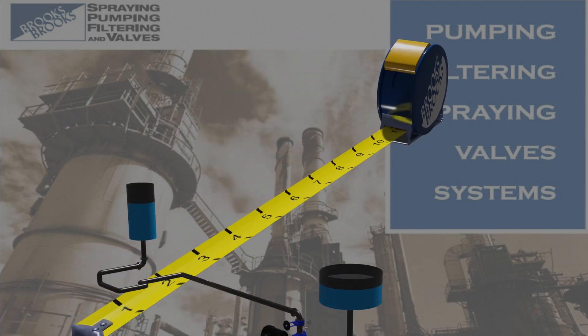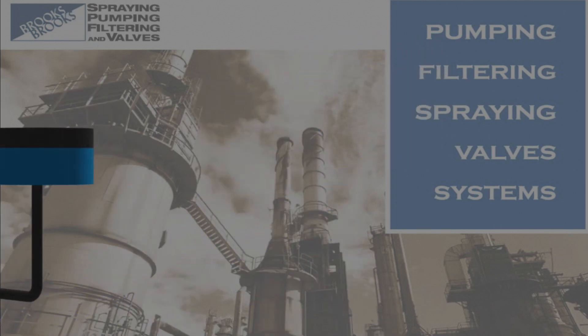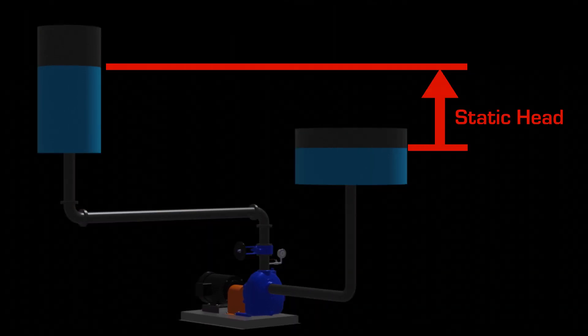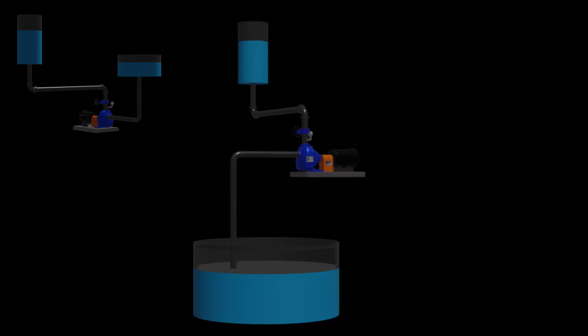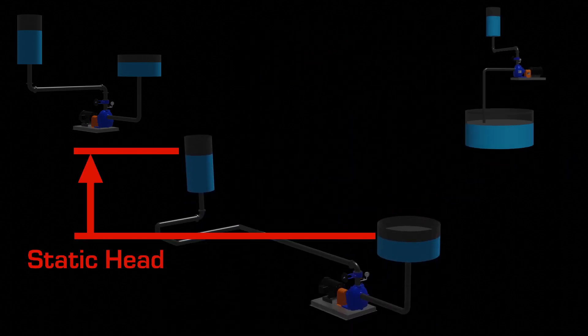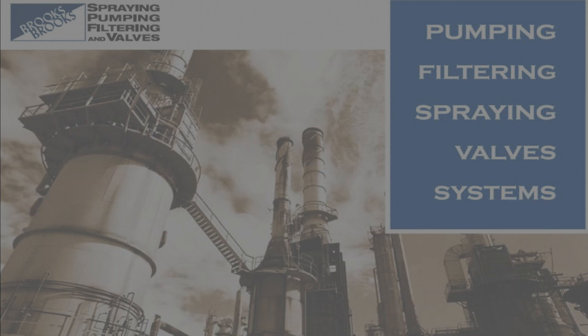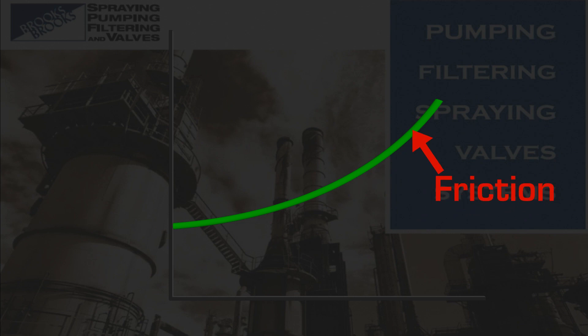Static head is easy to calculate — all you need is a tape measure or an accurate drawing of the system. The vertical distance from the source of the liquid to its highest point in the system is the static head. Be careful of piping systems that undulate, as siphons may develop. We will cover more about siphons in a later session.